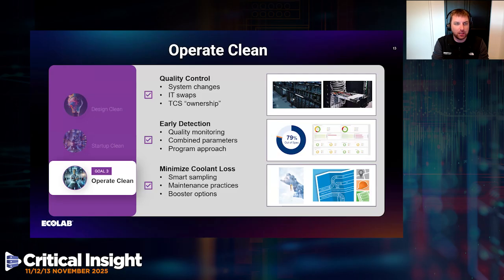How are we handling cleanliness there? How are we handling pollutants? How do we check for materials entering and exiting the system? And what we want you to consider is also that early detection is really important. So quality monitoring of the coolant employed is so critical to keep the loop tidy and nice and clean and in good working condition. We did an audit of around 200 cooling samples that have been analyzed by our lab. And we actually found out that 79% of these samples were out of spec on one or multiple parameters.